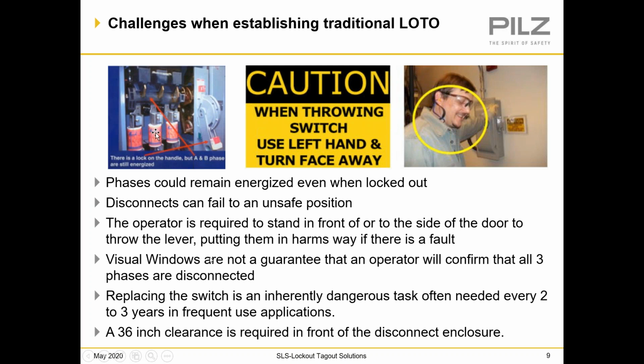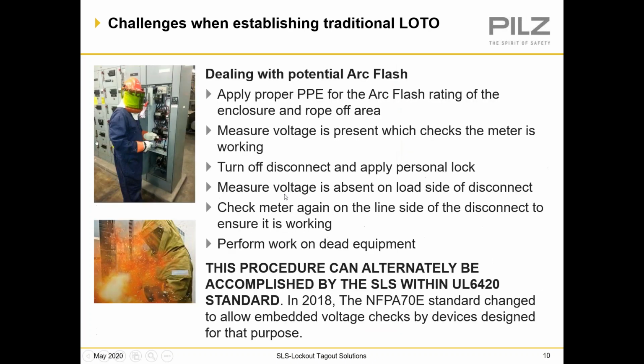And then replacing the switch is an inherently dangerous task, often needed every 2 to 3 years in frequent use applications. And you need at least 36 inches of clearance in front of the disconnect enclosure as part of the requirements for this type of traditional lockout procedure. The other issue with traditional lockout is dealing with arc flash.